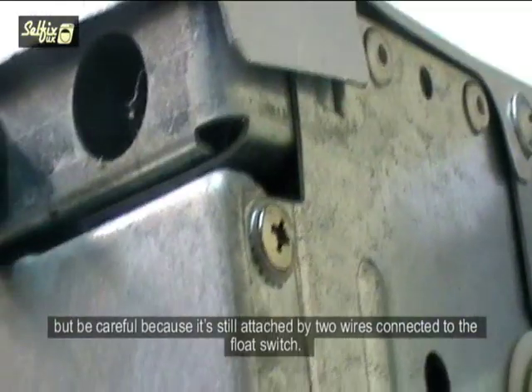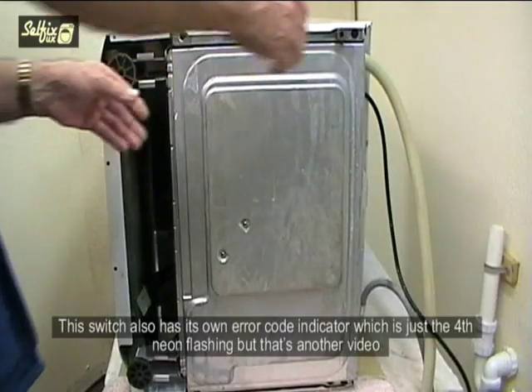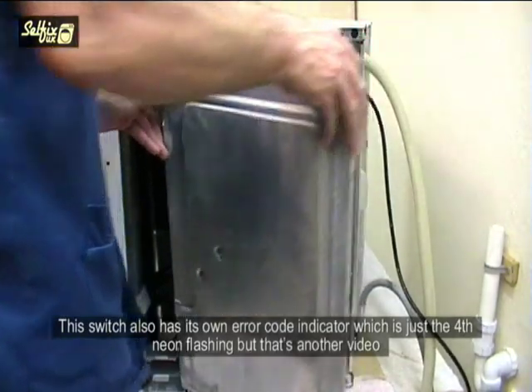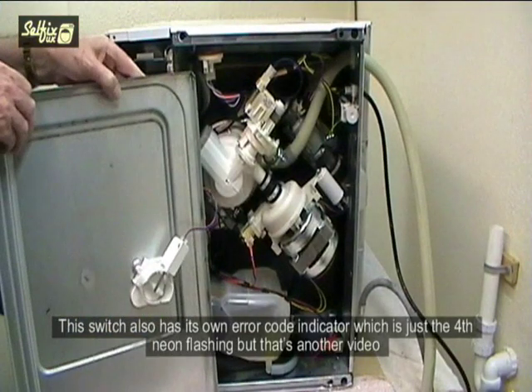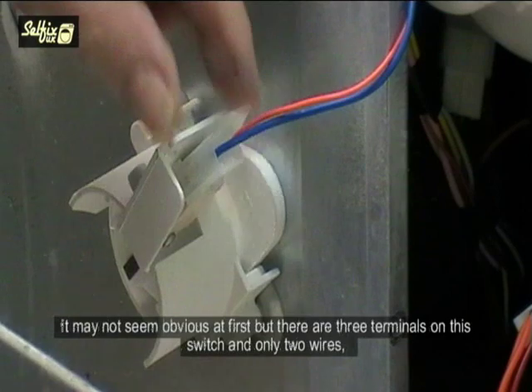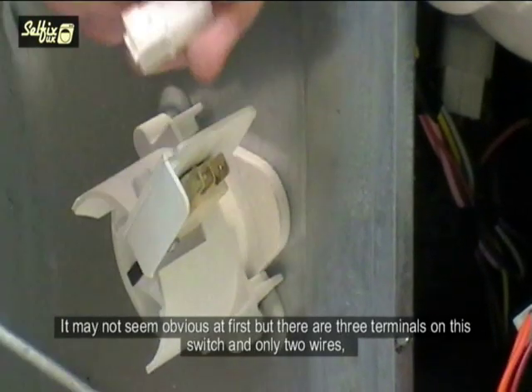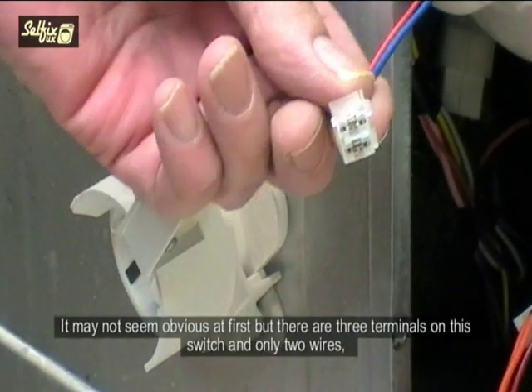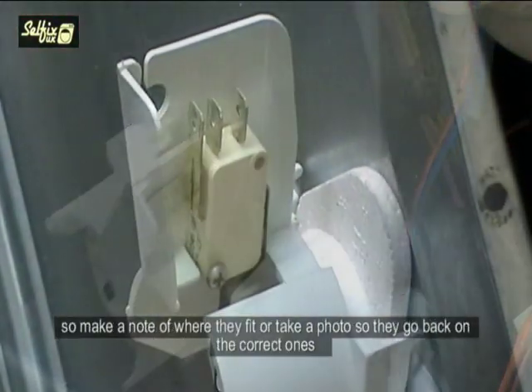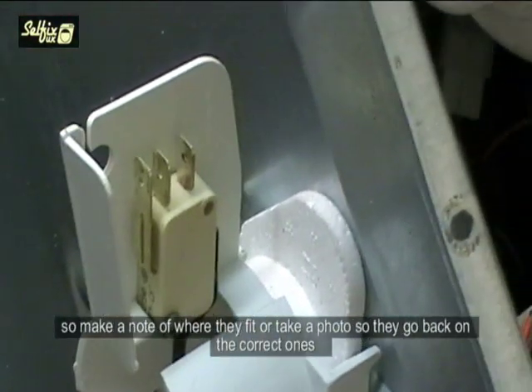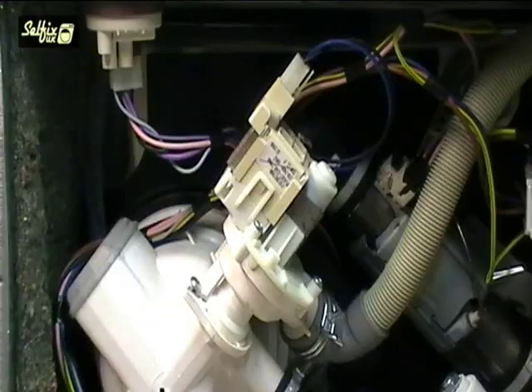When they've all been taken out it can be removed, but be careful because it's still attached by 2 wires connecting to the float switch. This switch also has its own error code indicator, which is just the 4th neon flashing, but that's another video. It may not seem obvious at first, but there are 3 terminals on this switch and only 2 wires, so make a note where they fit or take a photo so they go back on the correct ones.